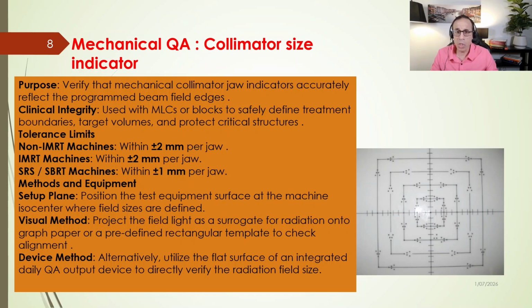Or sometimes on the Daily QA hardware, Daily QA detectors. Alternatively, we can use the surface of that device as a field size checking protocol for us.